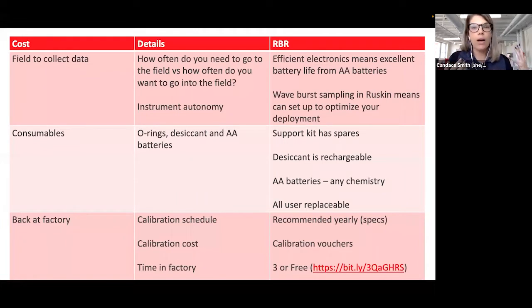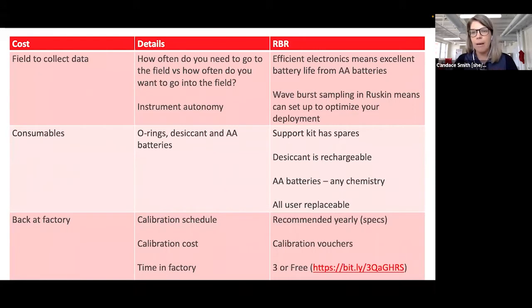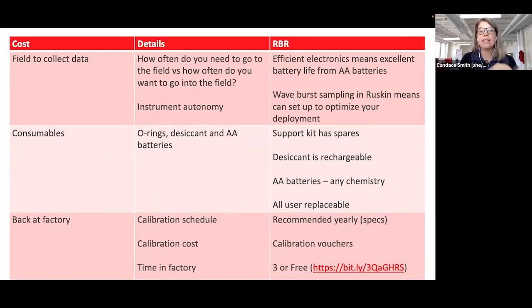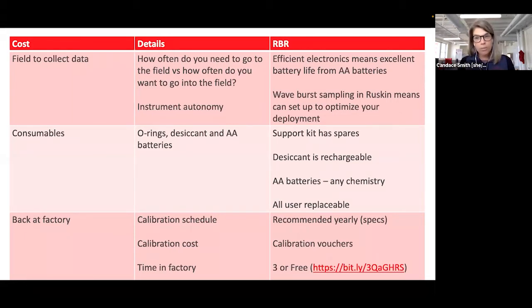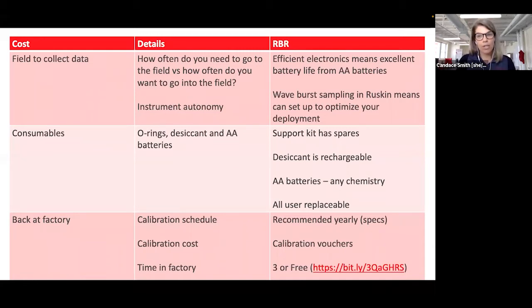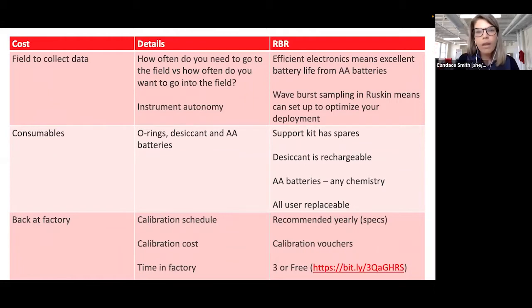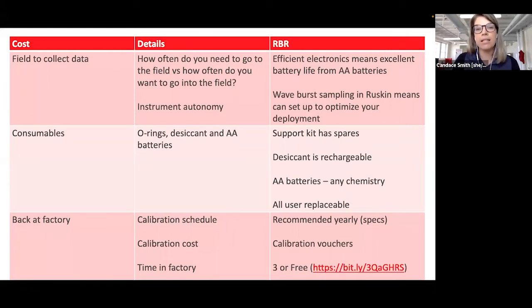The consumables at RBR: we have three consumables — O-rings, desiccant, and AA batteries. The support kit that comes with the logger actually has spare O-rings and spare desiccant. The desiccant is rechargeable. The AA batteries can be any chemistry, so you can use alkalines if you don't want to use lithium batteries. These are all user-replaceable, so the consumables are actually relatively inexpensive costs when using RBR instruments.